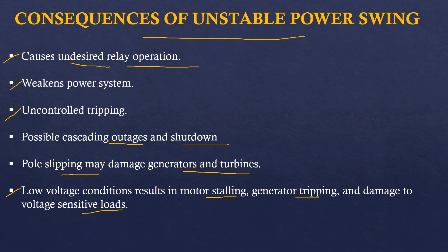Now, since we have studied the consequences of unstable power swing, there must be some protection technique applied to cope with this. Since we know that unstable power swings are the result of generators which have lost synchronism with respect to the other generators, the generators which are operating asynchronously must be separated and this separation must occur in a specified manner. The separation of the generators operating asynchronously will avoid damage to the equipment and will also avoid the possibility of a complete shutdown.